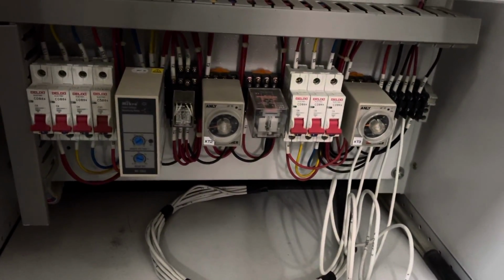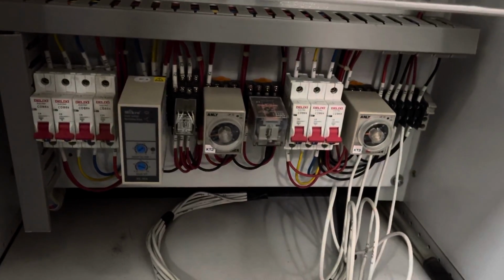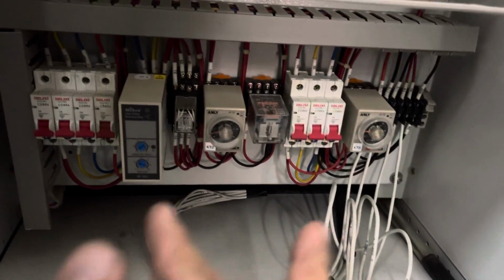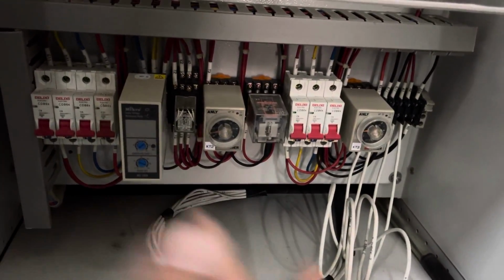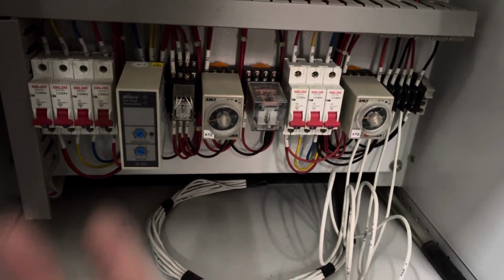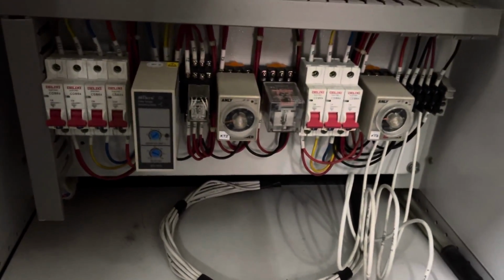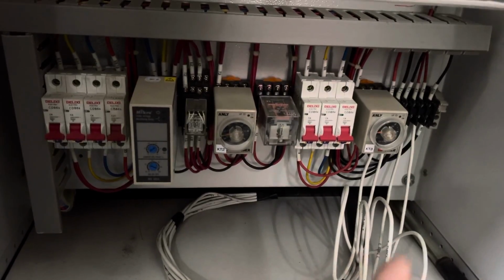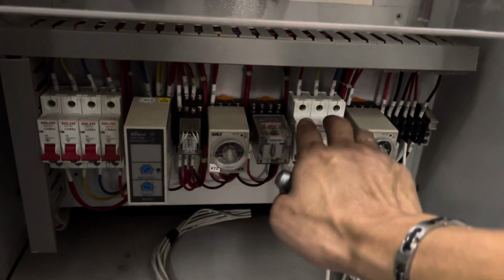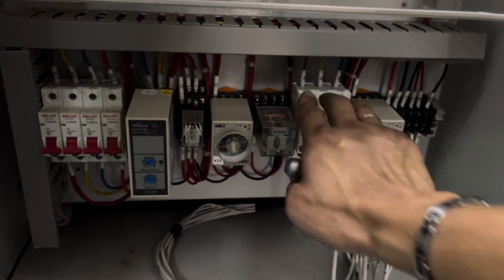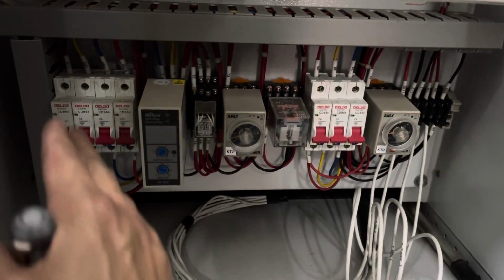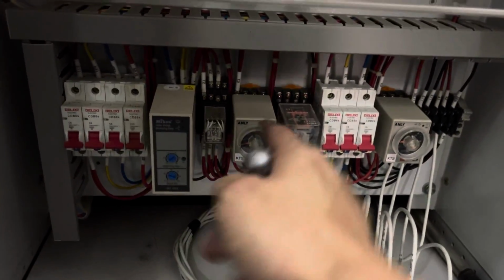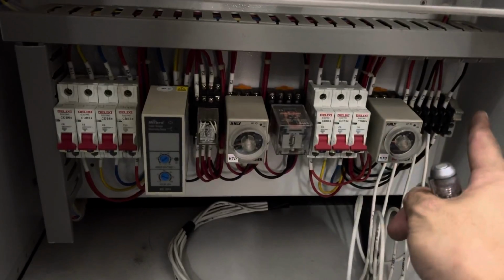Okay. So now, we are going to normalize it because we are not going to test the genset running for 1 hour. We just want to test the genset running for 5 minutes. Okay. So now, as I normalize, don't switch on the genset MCB first. Switch on the main supply MCB first, because if you switch on this side, it will change over.